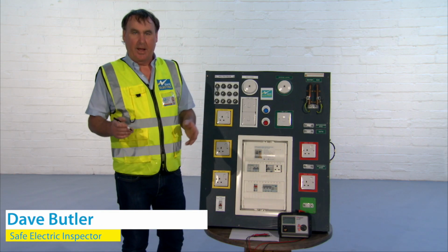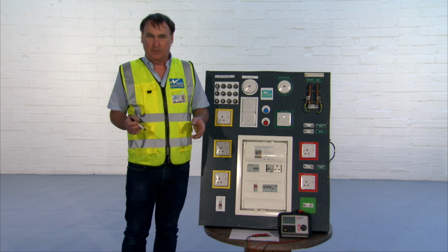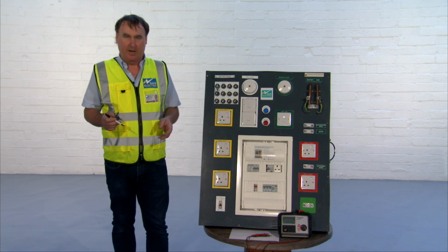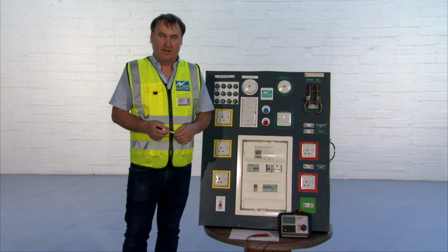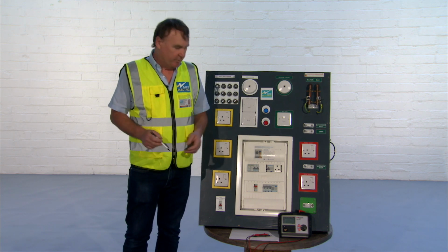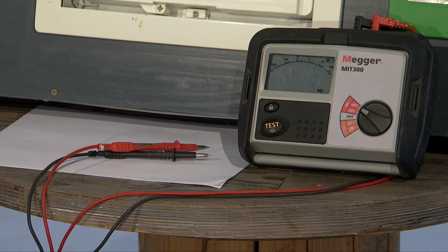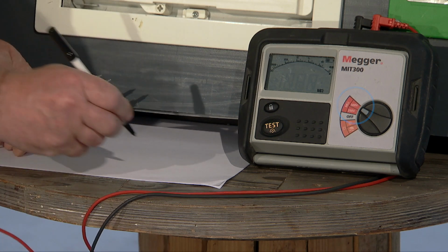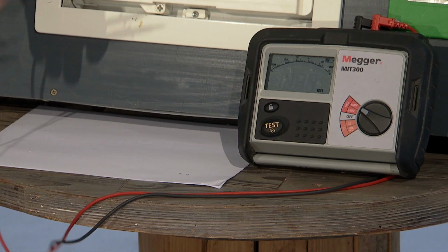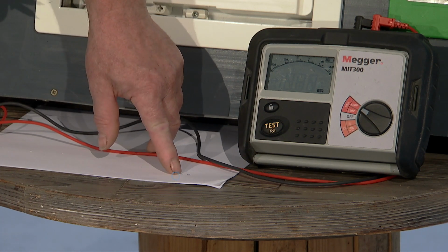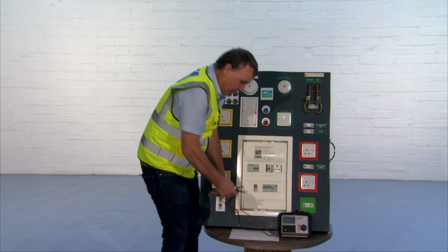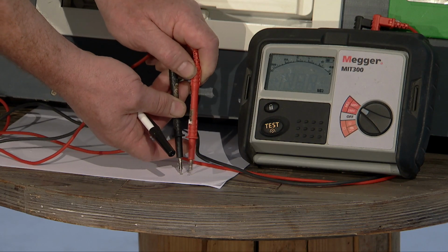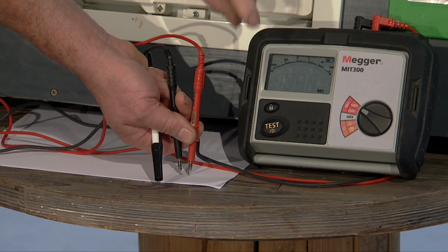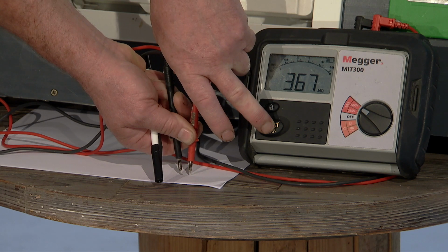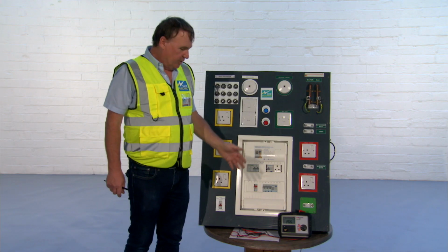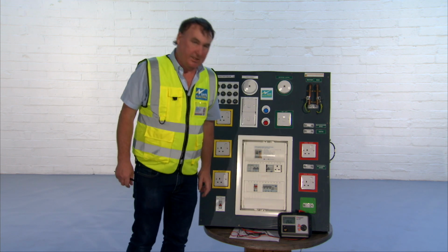I'm just going to explain a little phenomenon which happens when we're carrying out insulation resistance testing. And I'm sure that all you guys, as registered electrical contractors, while carrying out insulation resistance tests, have seen the value start and then start to creep upwards. I'm going to explain why this happens. I have my meter here, which is set at 500 volts for insulation resistance. I'm now going to draw two little spots on this piece of paper. And what I'm going to do is measure the insulation resistance between this point and this point on this piece of paper, okay? I'm going to expect this value to be very high because paper is a good insulator. So I'll hold the meter there, press the button, and our insulation resistance there is 372 mega ohms. So we've achieved a very high value of insulation resistance across these two little dots on that piece of paper.